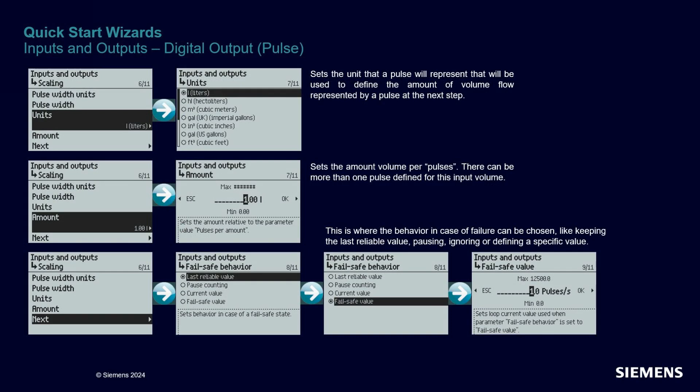Next, you select the meaning of the pulses in terms of units and volume. The last step is to select the desired behavior of the pulse output when the flow measurement is not available. You have four options, from using the last good value to stopping the count or using a failsafe value.